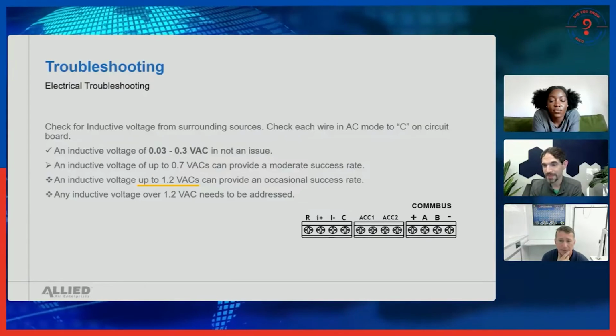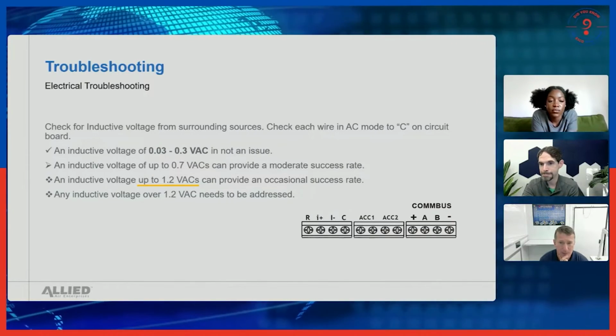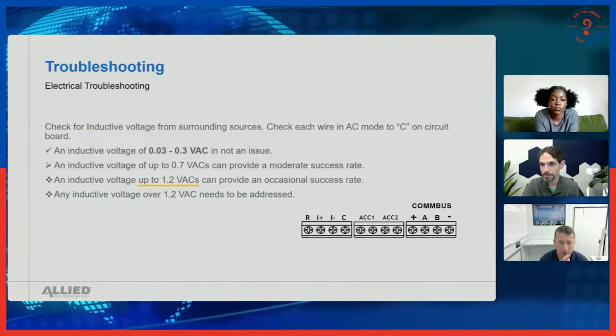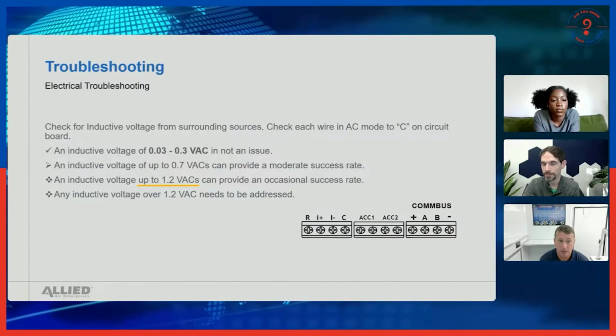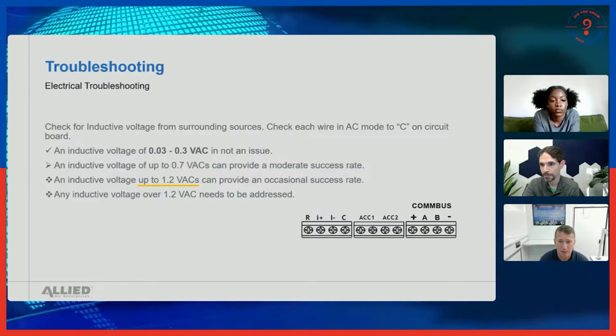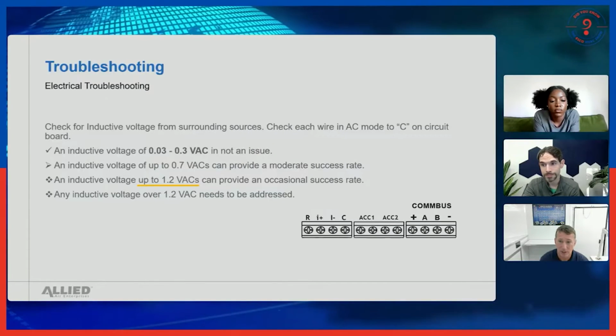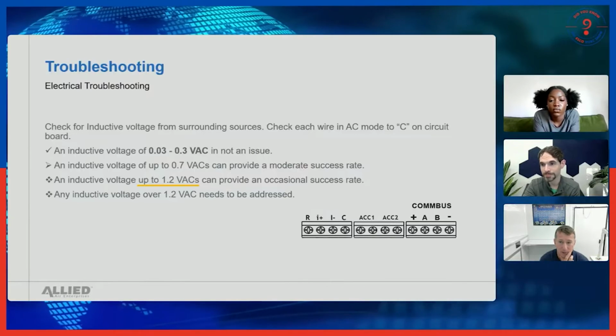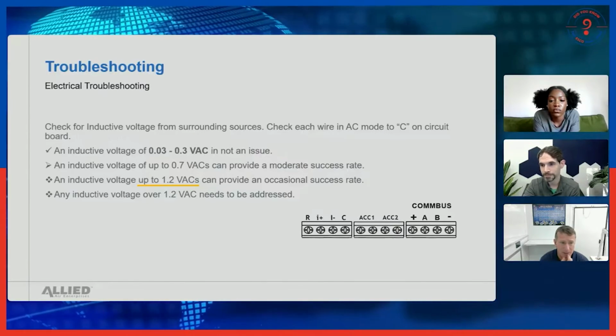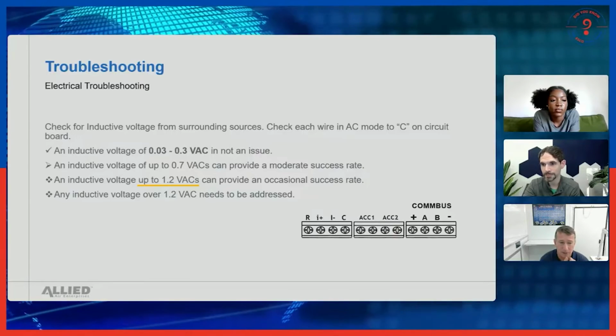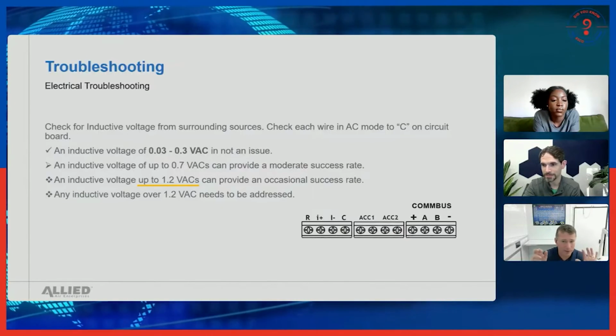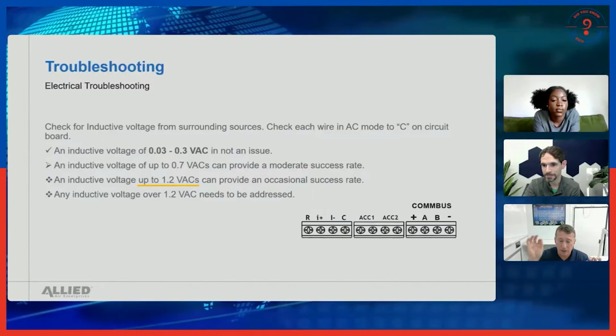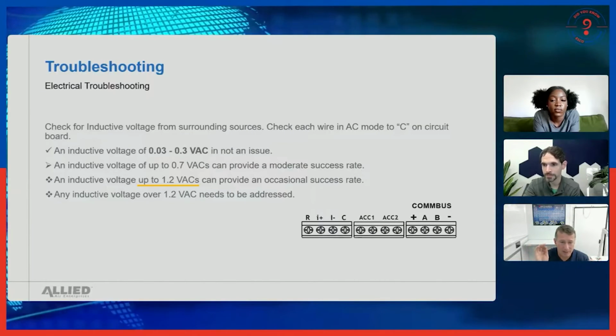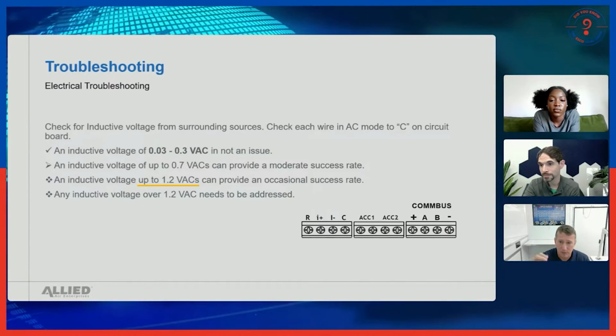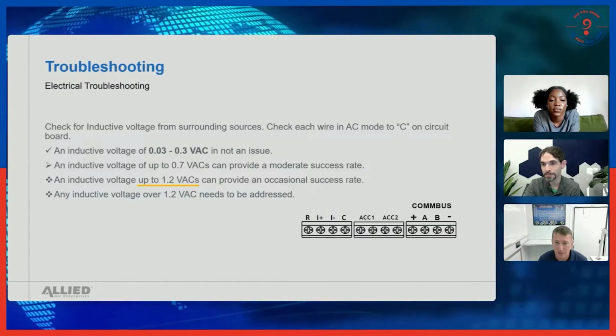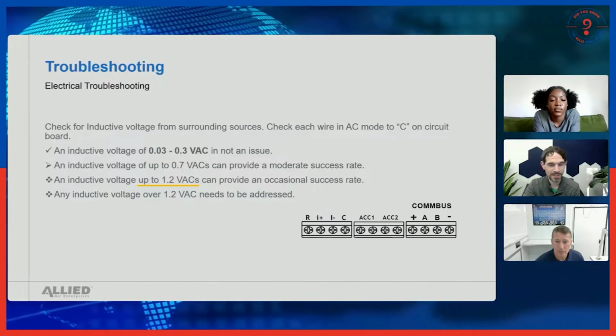I have never had anyone mention just measuring inductive voltage on the thermostat wires before—it's brilliant. Many times it's stapled right next to a high voltage line on the stud, and any staples or breaks in that wire could cause us to pick up inductive voltage on that DC signal. So we're literally just taking our thermostat wires and going from common or ground to each one of the wires to see if we're measuring the voltage induced by AC lines, outlets, switches, everything. I can't wait to try that now.